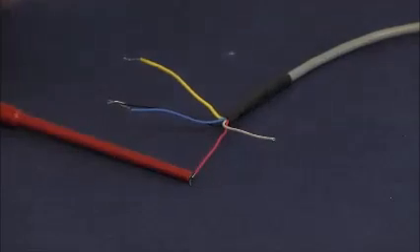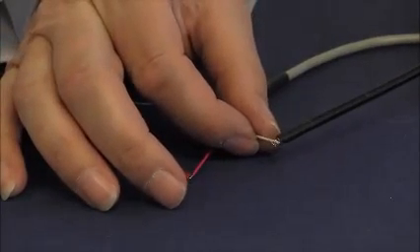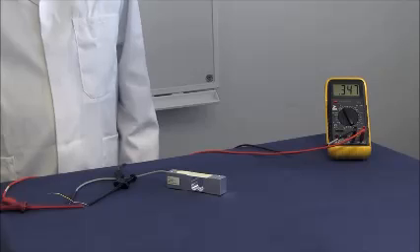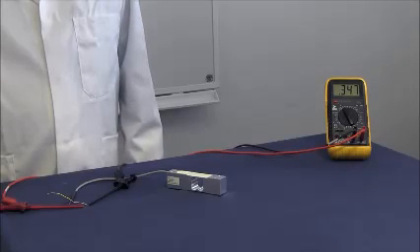Then carry out the test for the resistance between the measurement signal inputs as well, red and white cables with HBM devices. The feedback lines of the 6-wire circuit are not taken into account.